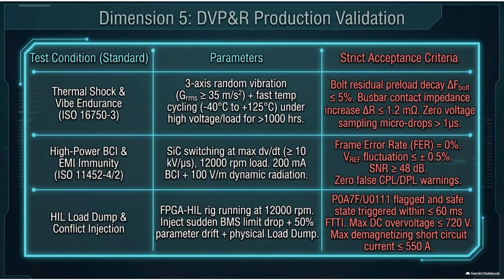But surviving the physical world is only one hurdle, right? The DVP&R also requires surviving electromagnetic warfare. Oh yeah, this test is intense. While the inverter is driving a dynamometer load, spinning the motor at maximum speeds approaching 12,000 RPM, test engineers basically bombard the casing and the wiring harnesses with massive external high-frequency radiation. Just blasting it. Yeah, they utilize bulk current injection, clamping inductive probes directly onto the communication lines to actively force heavy RF noise right into the CAN network.